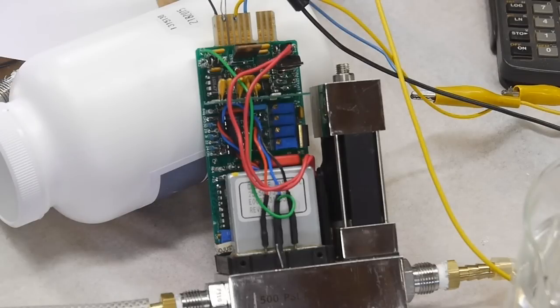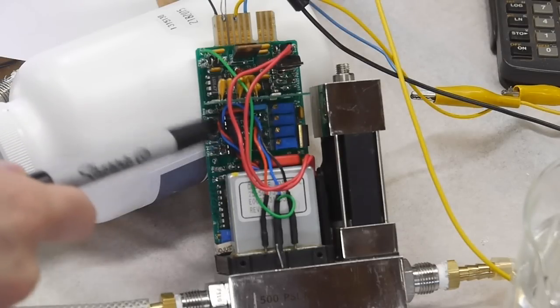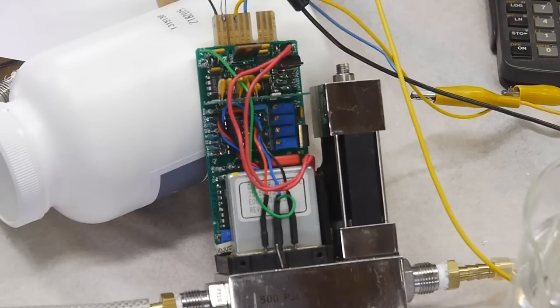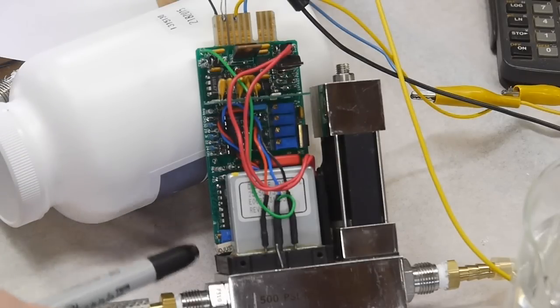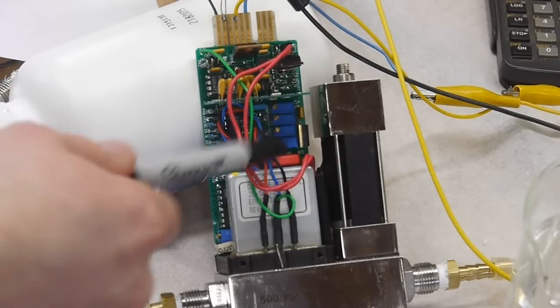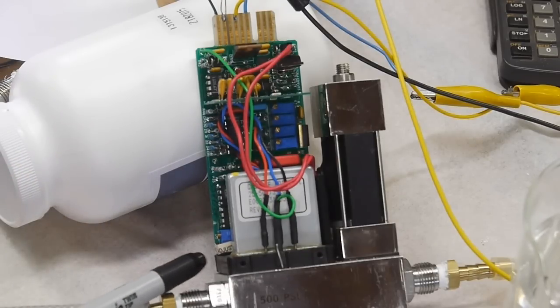Here's a closer look at the flow controller itself, inside there there's actually an LM324 quad op amp and it's got a bunch of internal pots to set presumably slope and gain, internal gain stuff. There's only one pot exposed to the outside, there's a hole in the outside cover for calibration so apparently once all these other ones are set, in fact this one even has a do not adjust sticker on it, then the meter is good for anything.